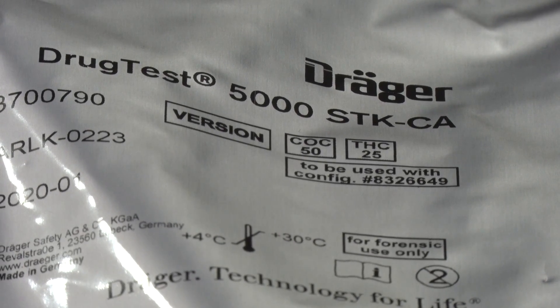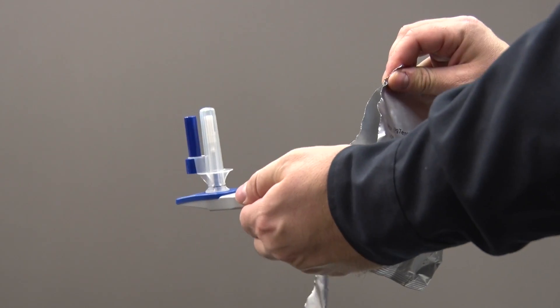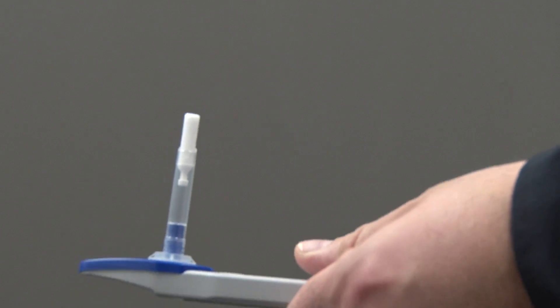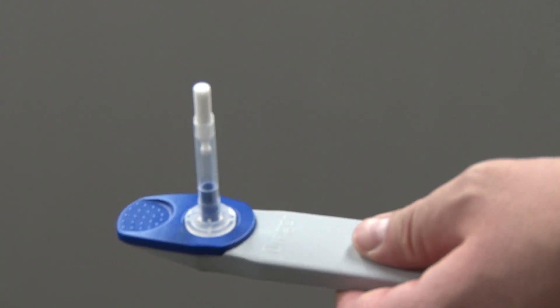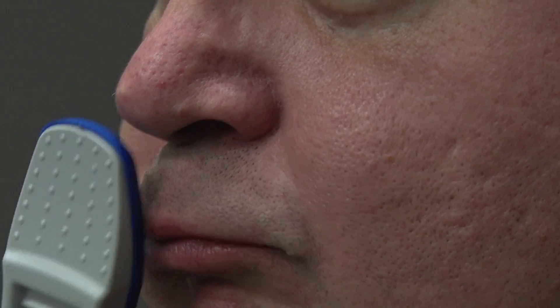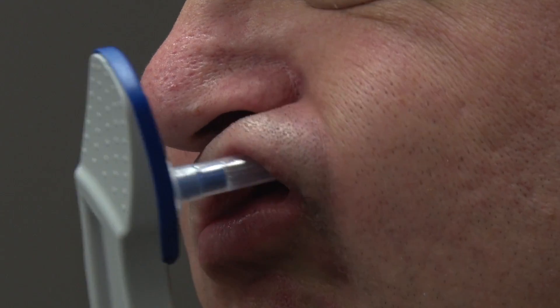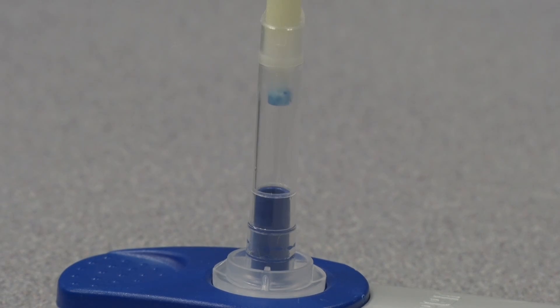In order to use the Draeger DrugTest 5000, the first step is to obtain the oral fluid sample. That's done by way of a cassette, which has a collector swab on it. The cassette is handed to the test subject and placed in their mouth by the person themselves. It usually takes about 30 seconds to a minute to collect enough fluid to proceed with the analysis.